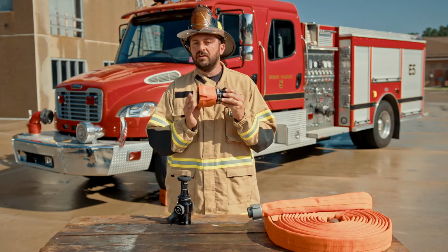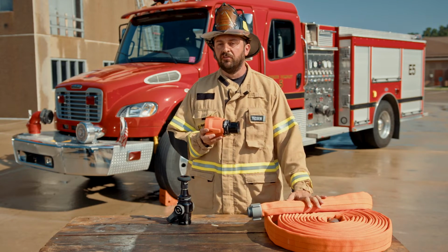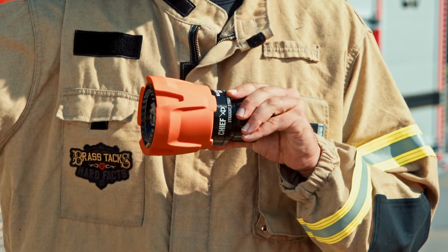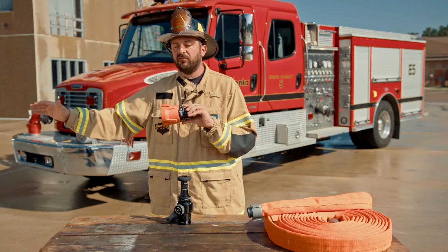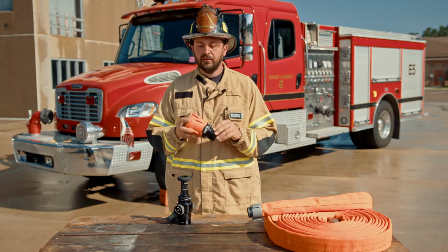So it would meet the Freeman ratio. When this fog nozzle reached 50 PSI, there would be 21 feet per second of water traveling through this hose. It would get to an area that is 1/4 the size and it would accelerate to 85 feet per second. And it will put down lots of fire with a low reaction force. That's the benefit of the 50 PSI nozzle.